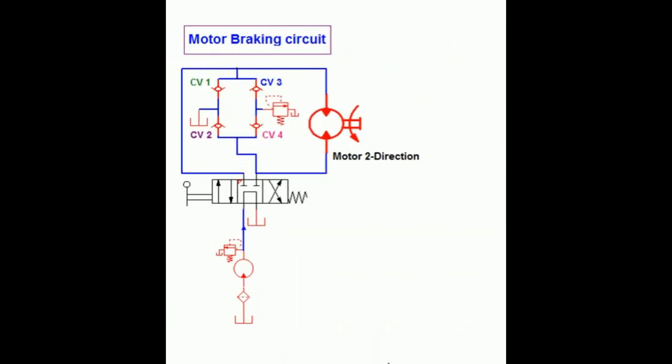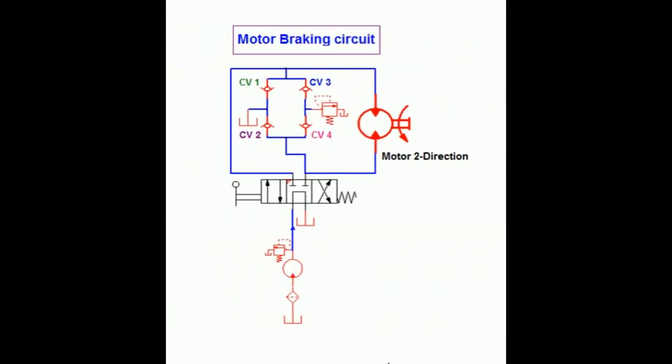The motor then acts as a pump, and a source of fluid must be available to prevent cavitation. To overcome these issues, check valves are fixed in circuit in this fashion. Let us see performance of system now.